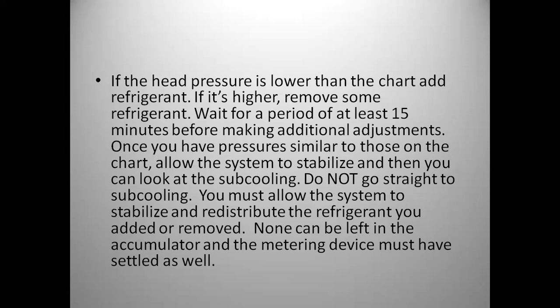let it stabilize. At that point, you'll want to dial in specifically to the subcooling. Your pressures are just kind of a ballpark, gross pressures to get you into the ballpark where you need to be, and then your subcooling will allow you to fine tune that. You must allow the system to stabilize and redistribute the refrigerant you added or removed. So every time you add some or remove some, you got to let it stabilize. None can be left in the accumulator, and the metering device must have settled as well.